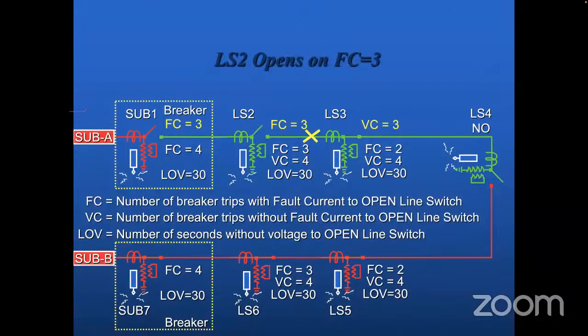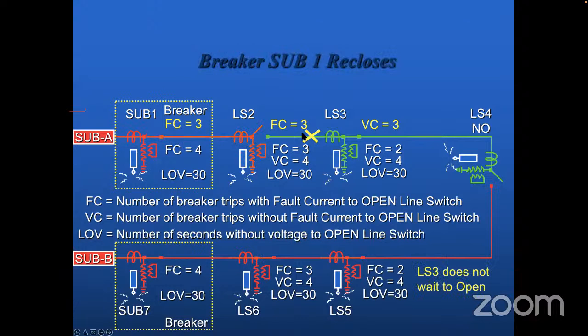Now as soon as it opens up, what happens? When you close this switch, all the customers in this area will get the power back. The fault is gone now. So there is no FC4 here - FC3 is done here. Now VC3 here. So what happens now? LS3 does not wait to open.